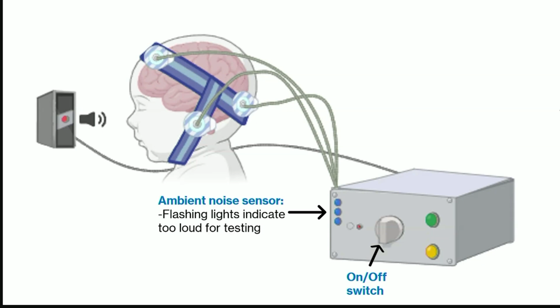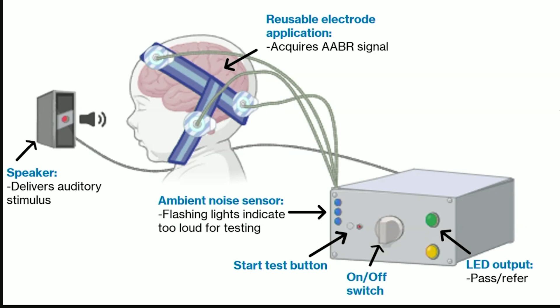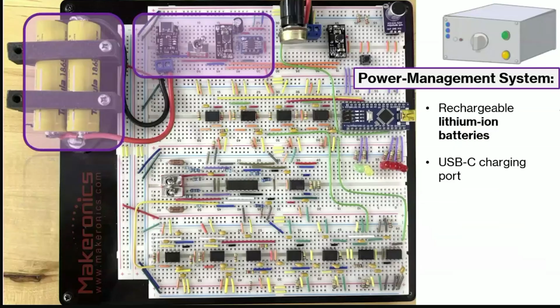Here's how our device works. First, we turn our device on, and our ambient sound sensing system assesses the level of ambient noise in the environment. If the level of noise is minimal, we press the Start Test button. A speaker then plays a 70 decibel series of clicks. Electrodes are used to acquire the brain waves from our patient. Our device then outputs a clinical result via our display LEDs.